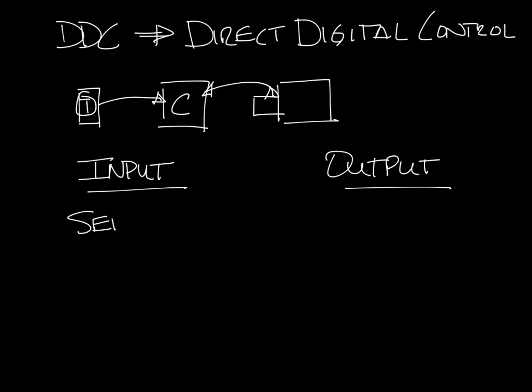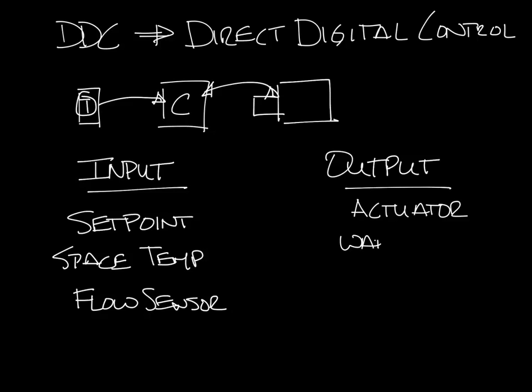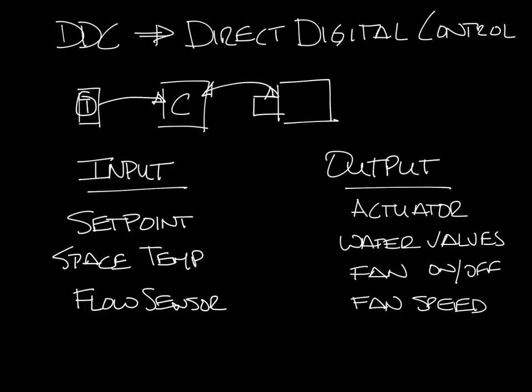Let's break down the operation of a VAV box and thermostat and label the inputs and outputs. The thermostat has a set point and measures space temperature, so these are both inputs to the controller. The VAV box's flow sensor is sending a pressure signal to the controller, so that's also an input. The controller is controlling the actuator that moves the dampers, the water valves that control the water coil, and turning the fan on and off — or possibly modulating the fan. All of these are outputs from the controller.